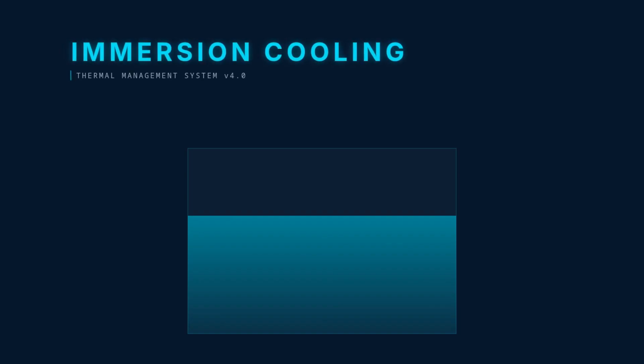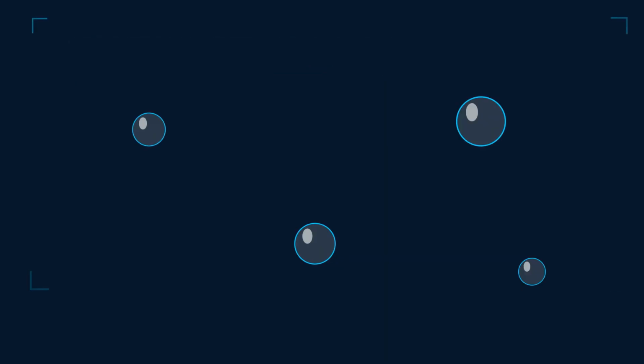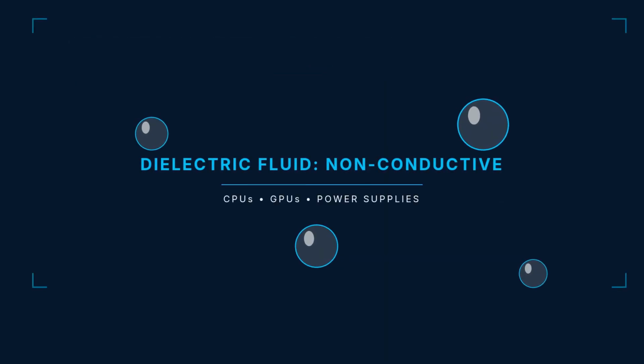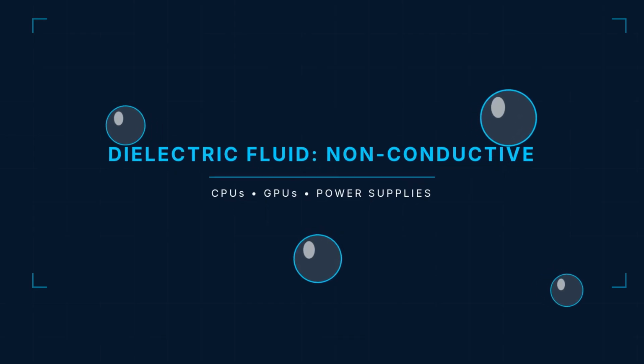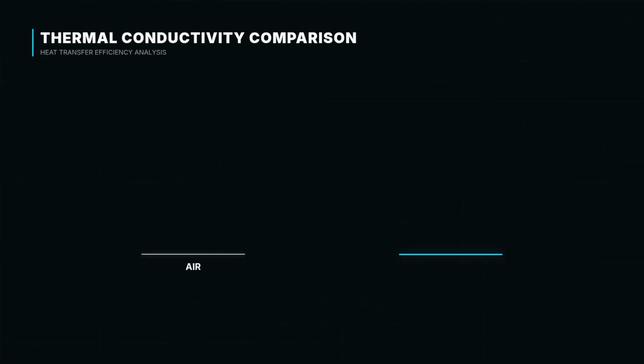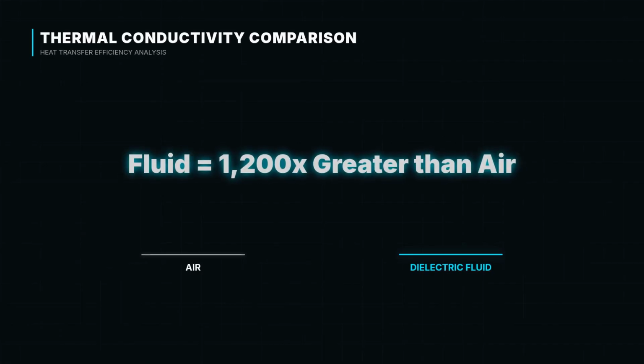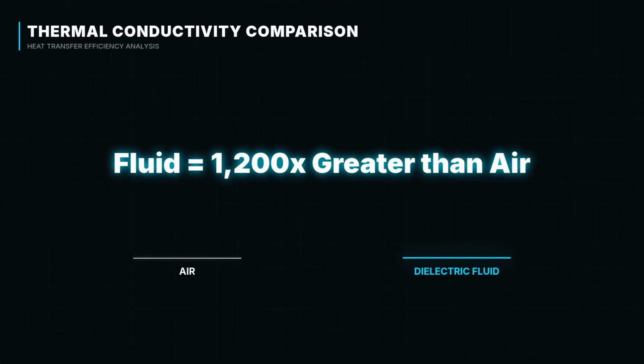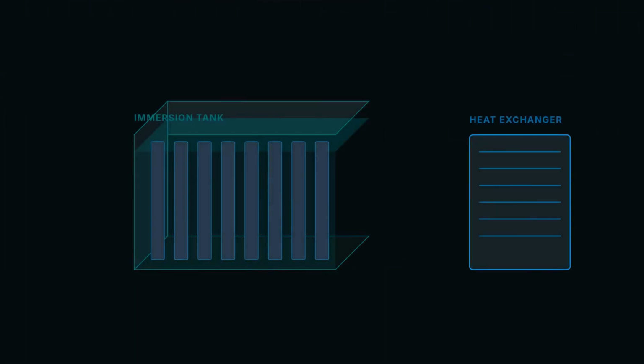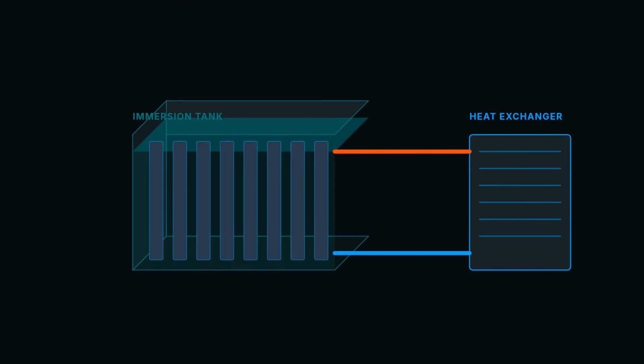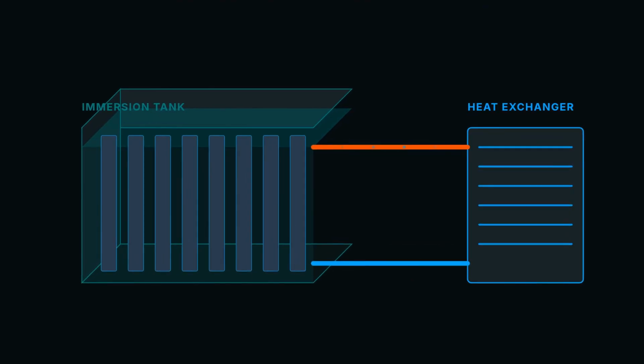The immersion cooling principle is a radical departure from conventional air cooling. It submerges server hardware, CPUs, GPUs, and power supplies directly into a bath of dielectric fluid. Dielectric fluid is electrically non-conductive, meaning it can contact live components without short-circuiting. The heat transfer is orders of magnitude more efficient than air because the fluid is in direct contact with the source. Hot fluid is pumped from the tank to an external heat exchanger, transferring heat to building cooling water.